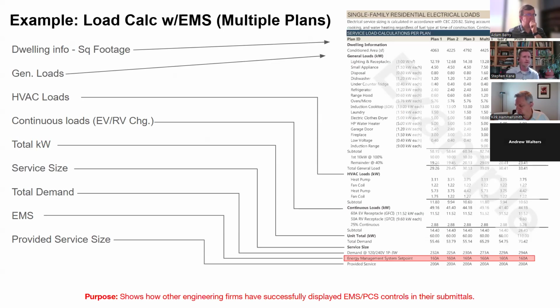So I'm showing an example load calc here where, some of you that are familiar with plan review activities, you've got multiple plan sets of different square footage of homes. And even with future electric loads, you have to include all of these potential ampere loads within your load calc. You're coming to a net result over 200 amps, in this example between 232 and up to 294 amps. But ultimately, noting that 750 and 220 article, you can just delineate the EMS set point on your plan set and determine that the service size can remain at 200 amps, even though the classic load calcs are coming in over 200 amps. So this is a pretty clean way to see it.